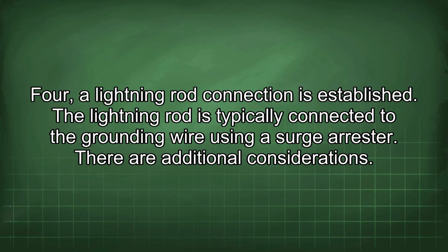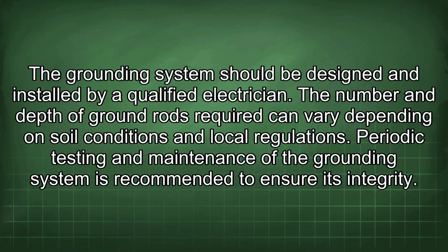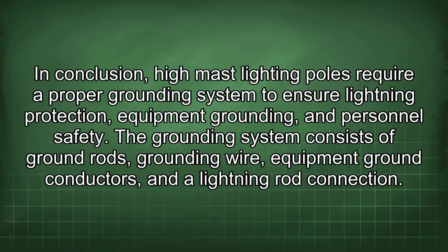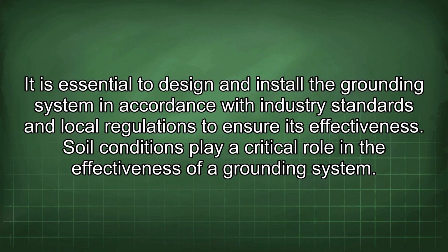There are additional considerations. The grounding system should be designed and installed by a qualified electrician. The number and depth of ground rods required can vary depending on soil conditions and local regulations. Periodic testing and maintenance of the grounding system is recommended to ensure its integrity. In conclusion, high-mast lighting poles require a proper grounding system to ensure lightning protection, equipment grounding, and personnel safety. The grounding system consists of ground rods, grounding wire, equipment ground conductors, and a lightning rod connection.